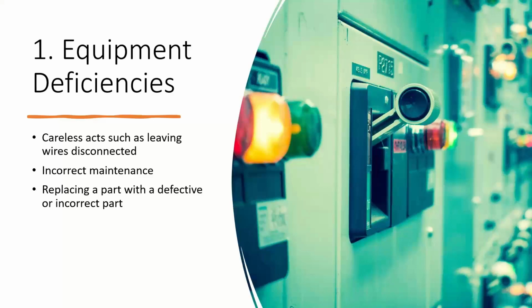Yeah. And what's an example of something that goes wrong when a wire is left disconnected? Well, obviously, if it's disconnected in such a way that it disables the function of, say, a protective relay, you could easily have a breaker in service that will never trip on a fault because there's a wire that's been left off. You could also leave a wire dangling so that it gets into the bus somewhere or into the higher voltage part of the breaker, and that could cause an arc flash at any time. Maybe when you rack the breaker, it causes it.